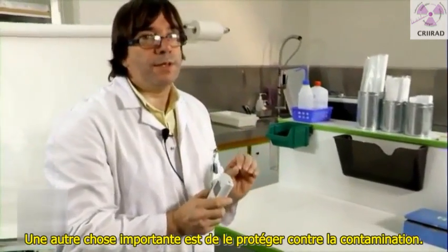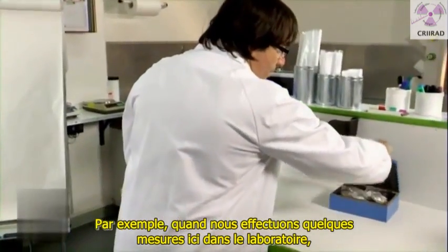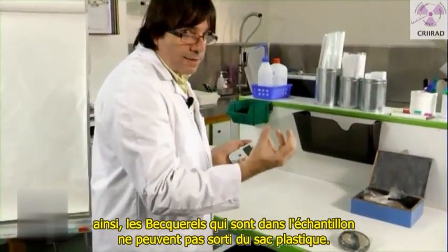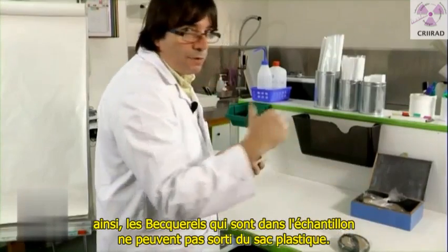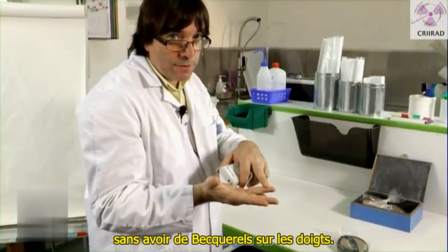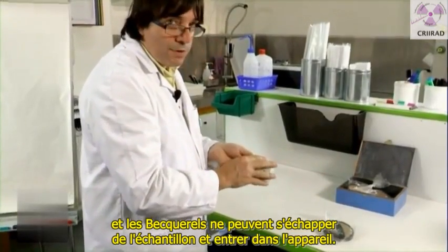One other important thing is to protect the device against contamination. For example, when we made measurements here in the laboratory, all the samples were put in plastic bags so that the Becquerels inside the sample cannot get out of the plastic bag. That's why I wear gloves. I can touch the sample and no Becquerels are on my fingers. I can put the device on the sample and no Becquerels can get out of the sample and enter into the device.